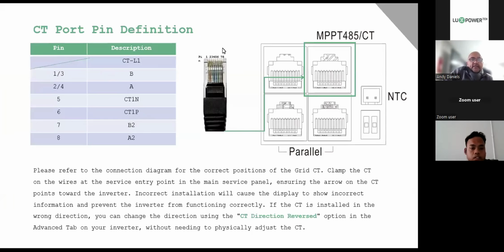Okay. All right, so the CT wiring, typically the CT only comes with 2 wires, which we use here. It's 5 and 6. And you can cut the CT and lengthen the cable, just color match the wires inside. It's a 2-wire cable that we supply with it. And I know in the LXP range, we do fit in a connector kit for the CT if you're going to lengthen the CT, but please make sure that you match up the wires. It's not just the simple case of connecting the wires. Sometimes it's a blue and a green wire, or green and brown. Make sure you go green to green, brown to brown, okay, when you extend the cables.